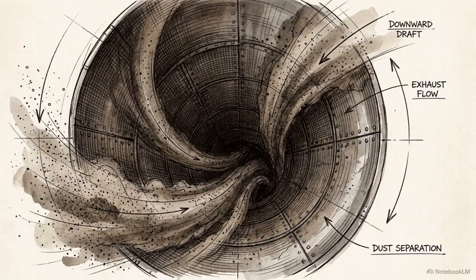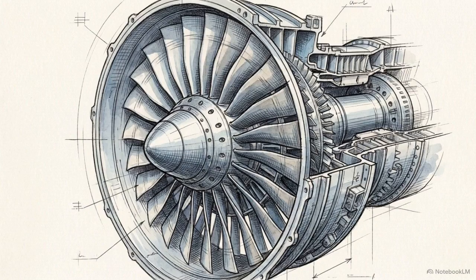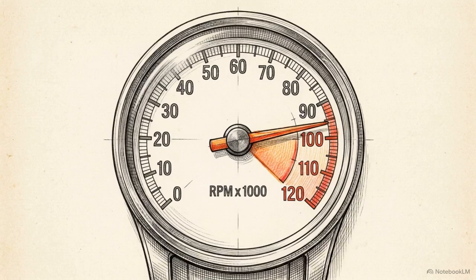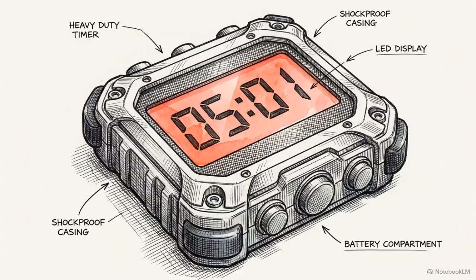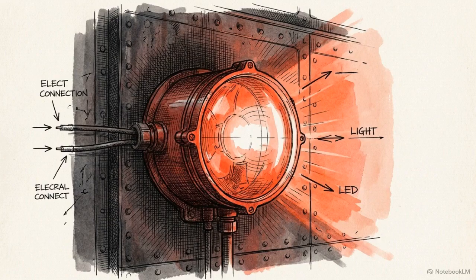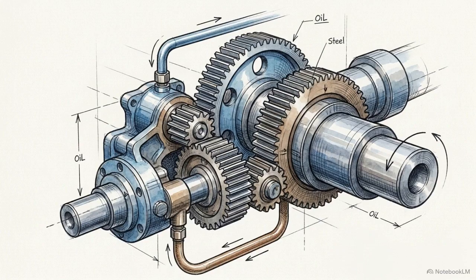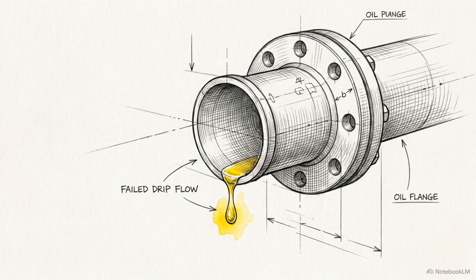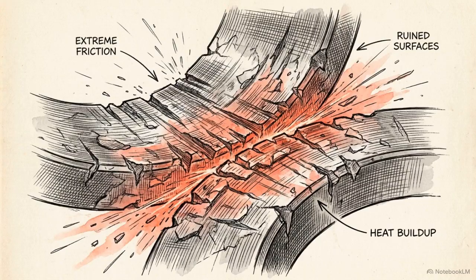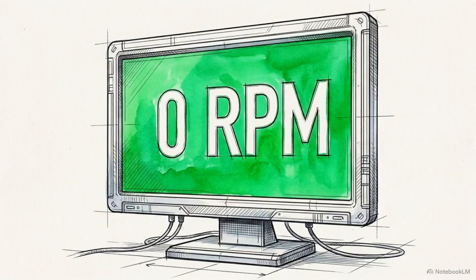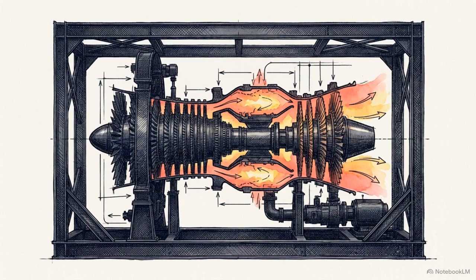There is a secondary risk even when the engine is off: windmilling. Unpowered external airflow through the exhaust stack can keep the shaft spinning for days. Windmilling between 100 and 1,000 RPM for more than 5 minutes is lethal to the machine. Because the lube pump is driven by the shaft, it cannot provide adequate oil at those speeds, and the dry friction destroys the bearings. 0 RPM is not a signal of safety. The invisible thermal momentum and residual airflow will destroy the asset if field engineers ignore the cooling requirements.